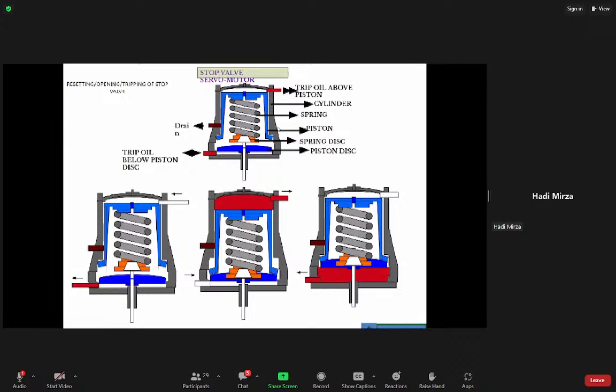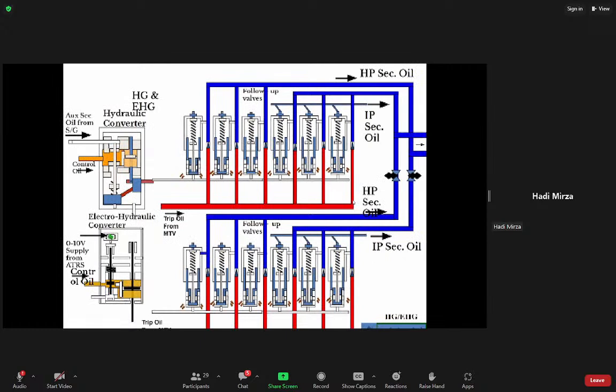These are the parts of the servo motor of the stop valve. This is the piston disc and spring disc. This is the piston. This is the spring cylinder, and trip oil pressure above the piston, and this is called below the piston. Initial condition, the servo motor will be like this without oil. After the trip oil reset condition, trip oil will be coming from here, and this spring will be compressed like this. And after the reset, this oil will be drained, and again trip oil from below the piston will enter from here, and the servo motor will be opened like this.